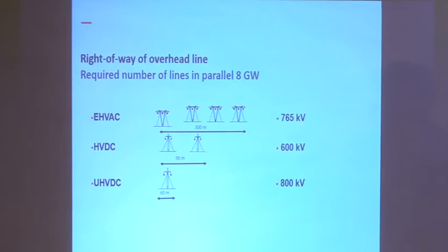From an environmental point of view, if we want to transmit 8,000 megawatt of power from one place to another using AC, we would need roughly around 300 meters of right of way for 1,000, 1,500, or 2,000 kilometers. Distance is not a constraint for DC. If we use DC at 800 kV to transmit the same 8,000 megawatt, we require only a 60 meter corridor. So it's only 1/5 of the right of way, which is a big benefit for the environment.